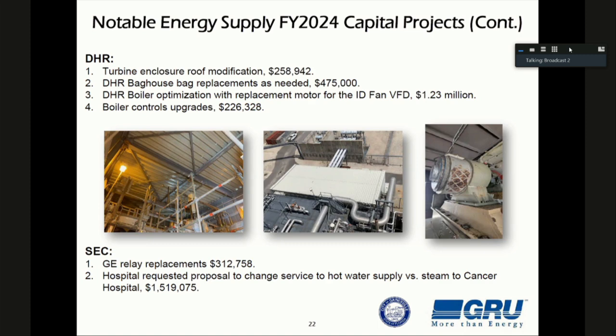We have a variable frequency project for the induced draft fan to the boiler, and primary air fans to the boiler. Both those VFD projects, and these are multi-year, 24 and 25, are going to reduce the size of those motors, reduce our load to around $300,000 of savings each year. So even though it's a capital investment, we'll have a reduction in our O&M true electrical cost of about $300,000 a year, let alone the wear and tear on the fans. It's a lot of wear and tear on the fan when you run it at full speed, using a damper to control flow. Whereas if you could use a motor to do it, we reduce the wear and tear on those components as well. So it's a cost savings for us.